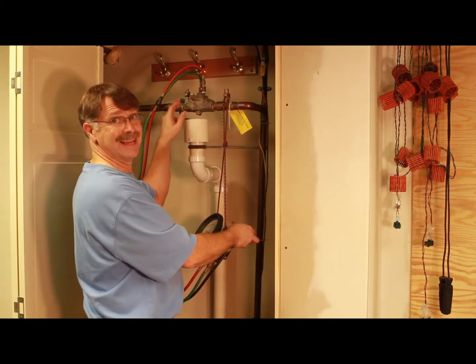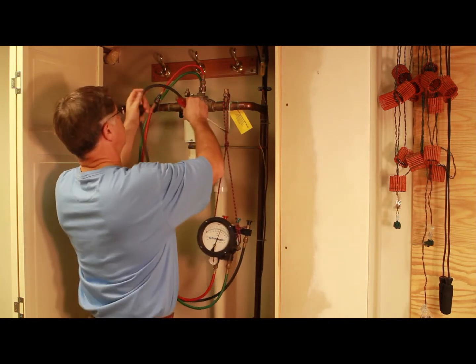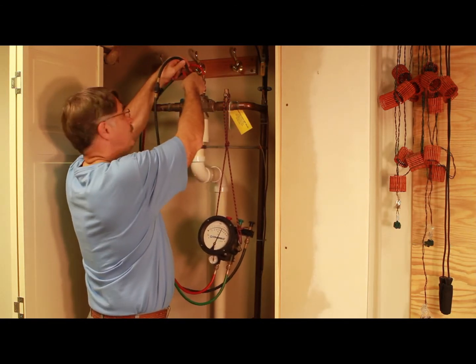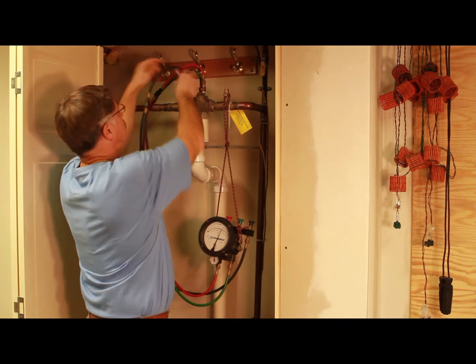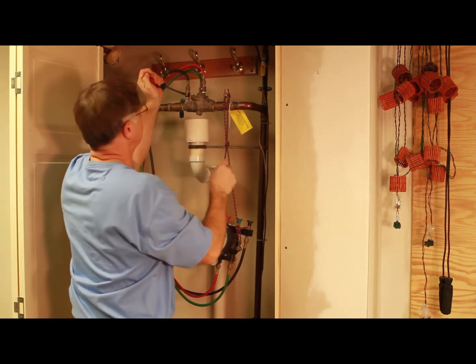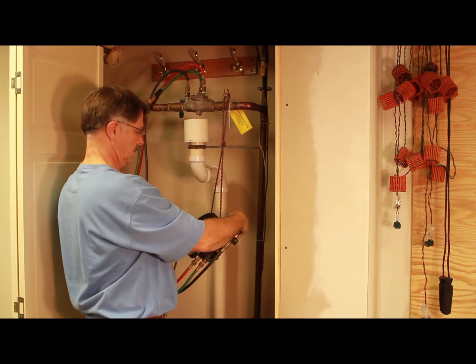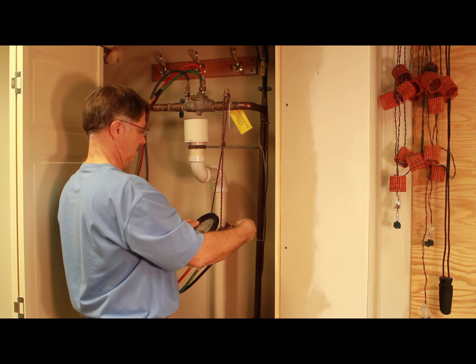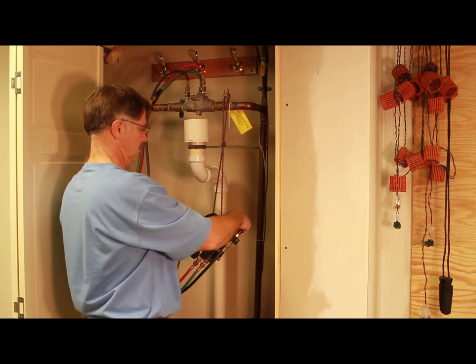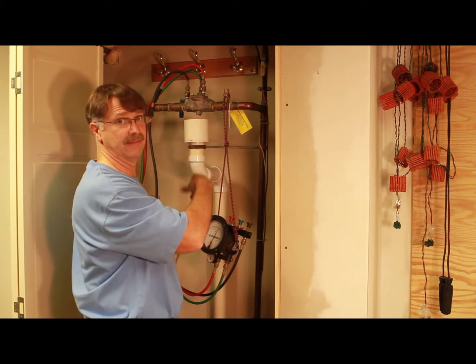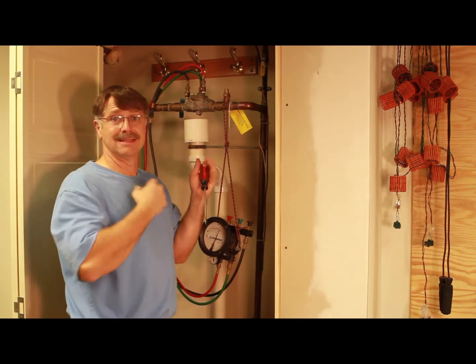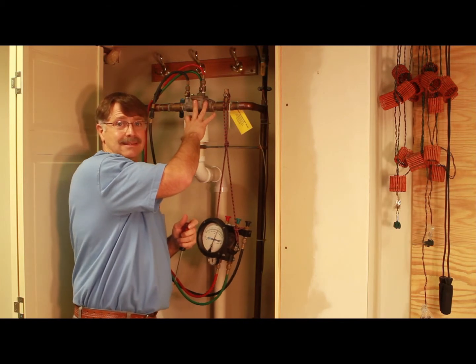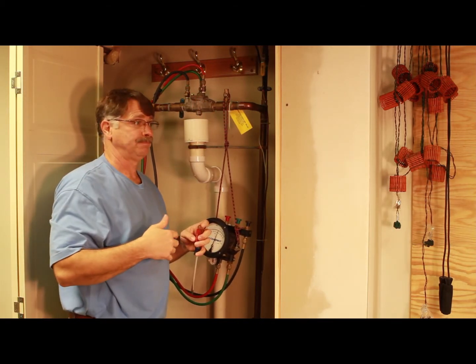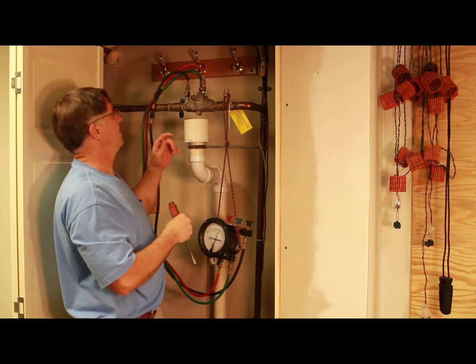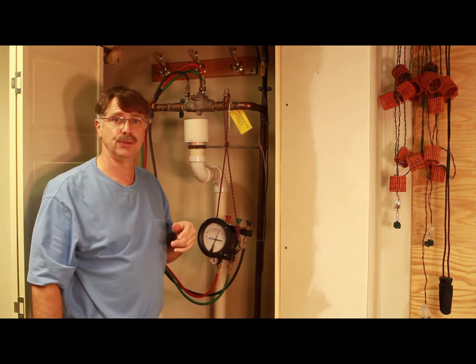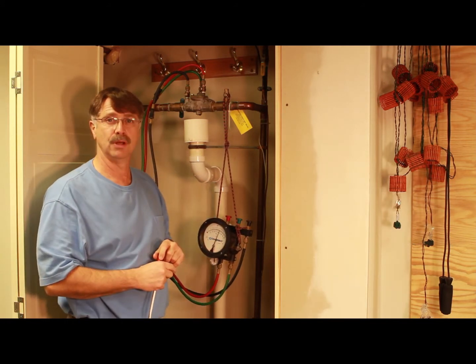And then the last section is testing the back. And to do that, I'm actually going to apply back pressure to it. And we're good. Well, except that I still have to fix the middle part. But that's the process. So annually we test this thing, make sure it works, and as long as it does, you'll never have water going back into your drinking water. You'll always be safe.